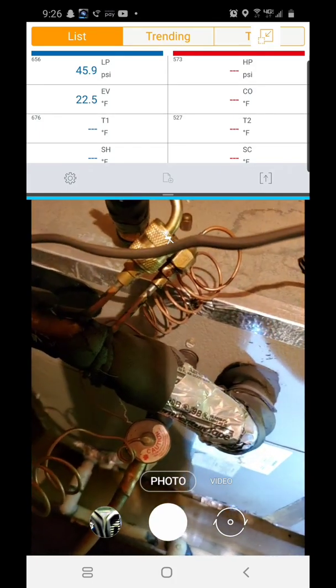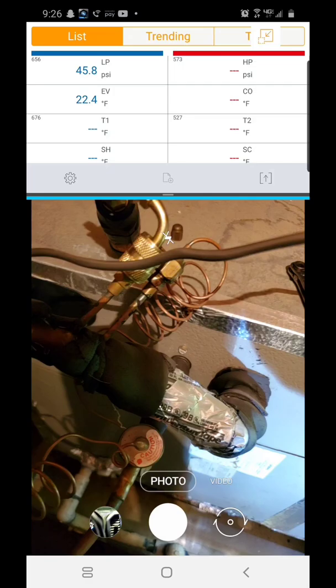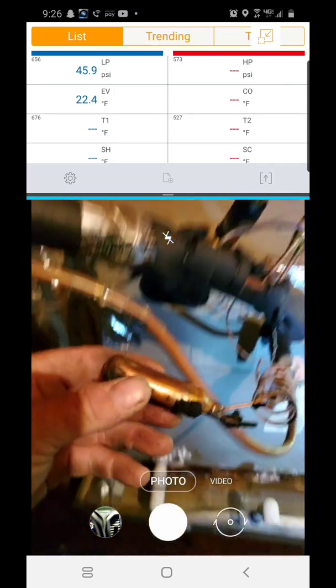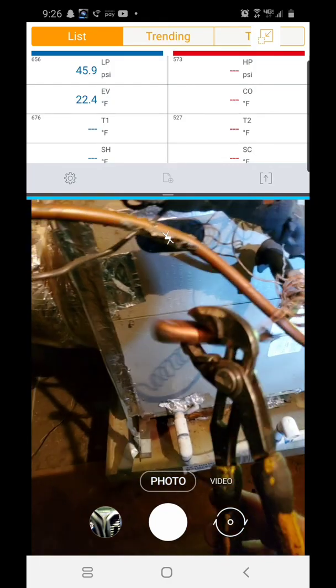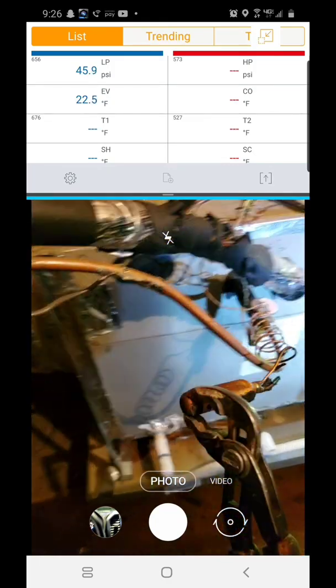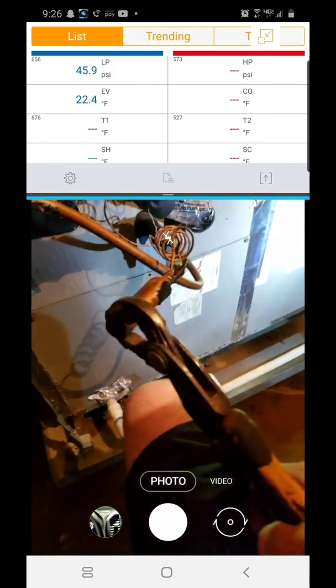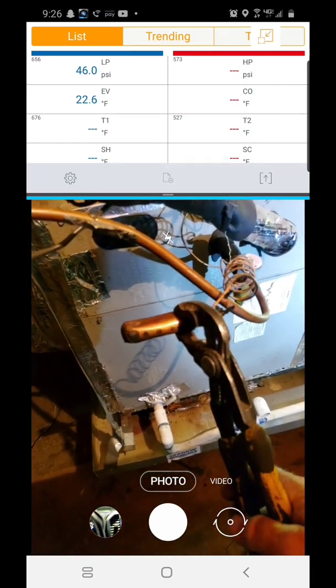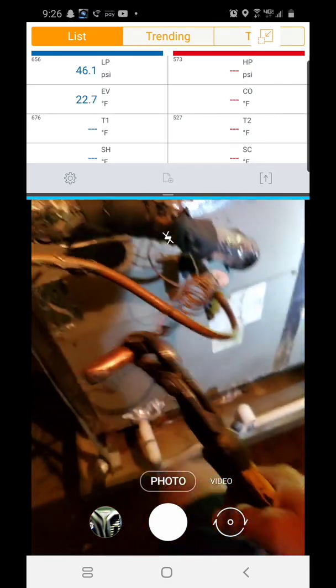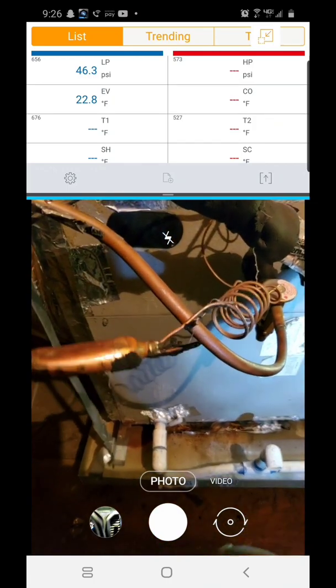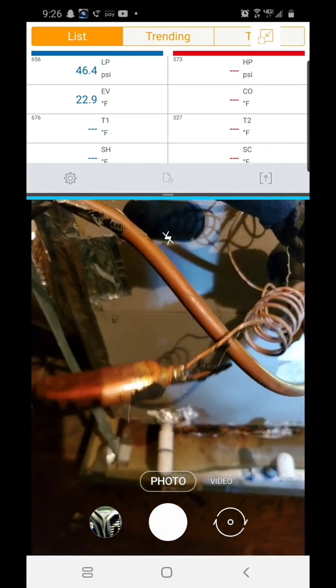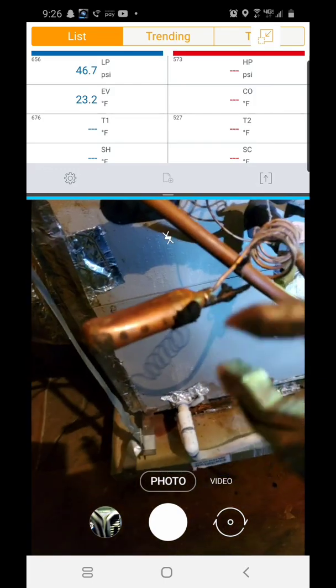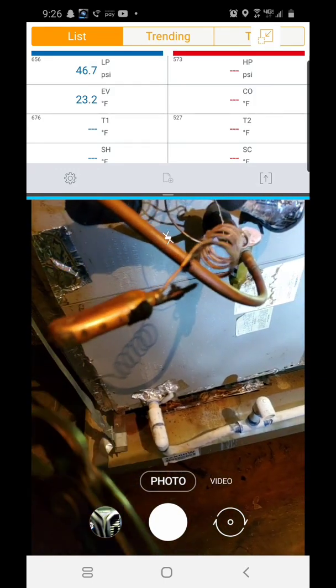It was down to about 30 psi, so I took this bulb off and I've been smashing it. I assume it's fubar'd. If this doesn't come up enough, if I could at least get it up towards 50 or so it might not freeze. I'm just trying different things, like smashing this piece of junk. You see the pressure, it actually seemed like it went up when I did that.